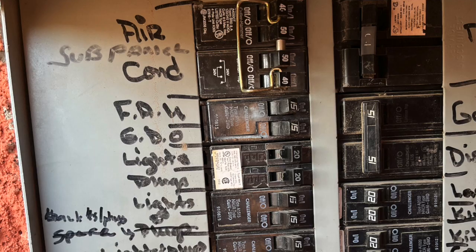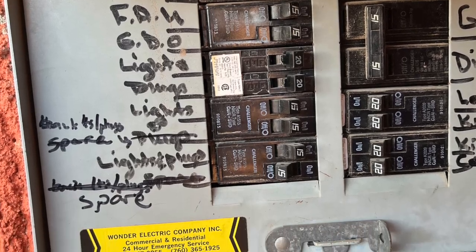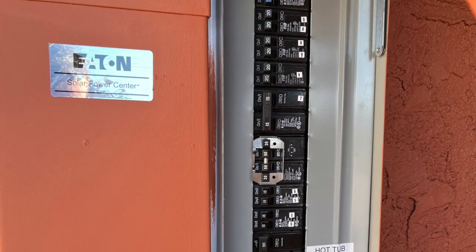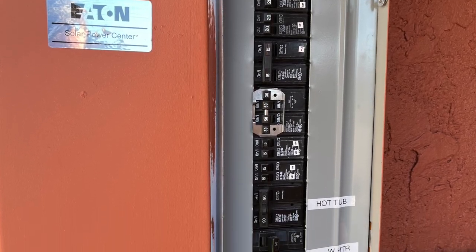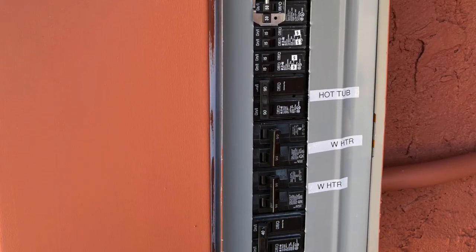That said, switching from storage to tankless can be quite expensive. We'll get into the details later on sizing, but depending on the unit you buy, you might need two, three, or even four 50-amp circuits to run a tankless water heater. If you have a 100-amp service, this probably isn't even going to be an option. In our case, we were upgrading to 200-amp service as part of our solar installation, so this was a little bit of an easier add-on for us.